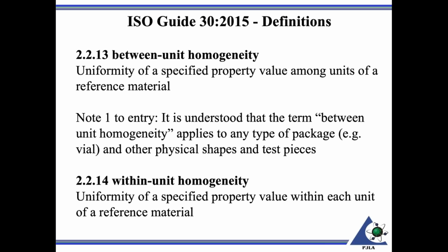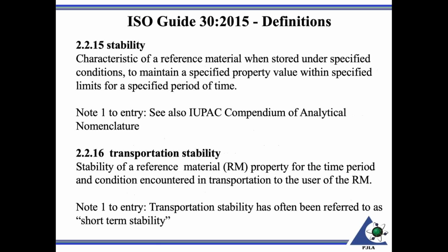So for example, there could be something that settles out in the unit and, before use, has to be agitated or sonicated or something of that nature. It could be a color related item. It could be mixing of the materials. It could be something that doesn't mix well, but you'd want it to be evenly distributed throughout the reference material and so forth. If your reference material is a hardness testing block, then you'd want to make sure that the block is made and presented such that you get a consistent value throughout the surface of the block.